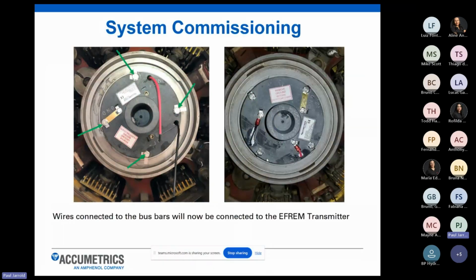So rather than a large collar that's split in half that we have to bolt to the outside of the brushless exciter shaft, we can mount this right on the end of the exciter, right in the center line. So this is like a snout. There are turns of wire cut on the outside of this snout. That's how we make our electrical connection, that rotary transformer connection between the rotor and stator. So the wiring gets landed directly to our transmitter, and the image on the right shows a more finalized picture of what that looks like when it's installed.